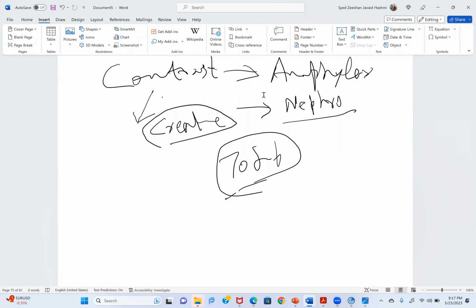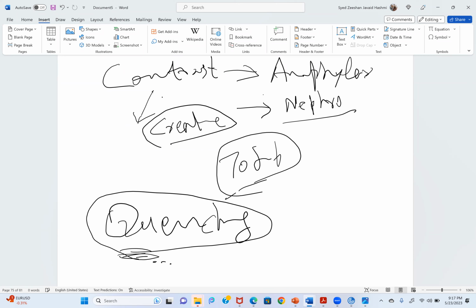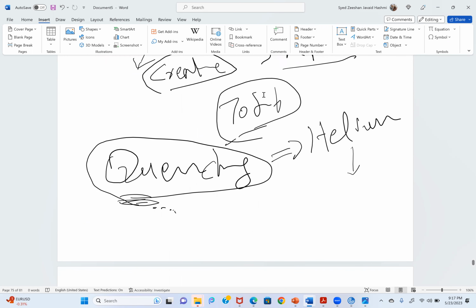Okay. So another important thing which you should be knowing is quenching. This is in relation to MRI dysfunction. And the problem is that helium is released. So there is a system of monitoring the release of helium. Because if helium is suddenly released, there will be hypoxia, not to the patient, but to the environment. And there is an oxygen sensor, and a mechanism by which they are monitoring it, because if there is any malfunction, they need to quench, and the helium will be released. So you should know that there should be an oxygen sensor, and you need to abandon the scan. Of course the scan will be abandoned, and even if the patient moves a little bit, maybe the scan will not be successful. So you need to do the scan from the start. Okay. So these are the challenges which you have.